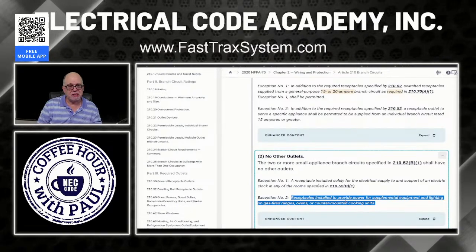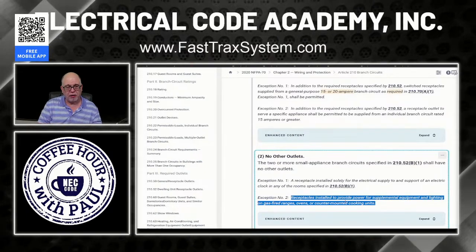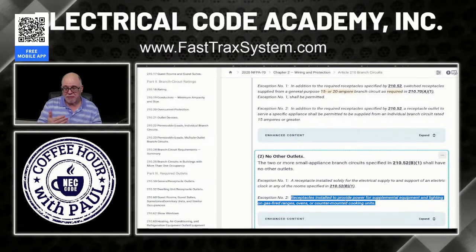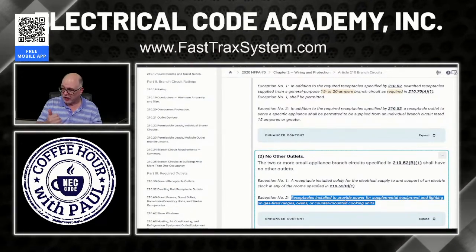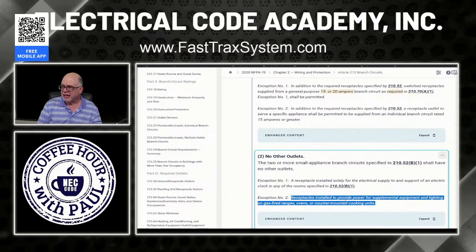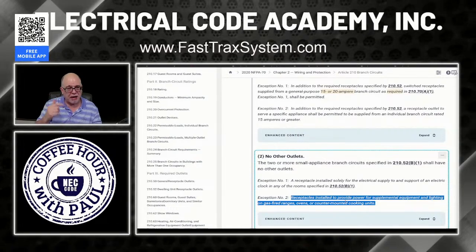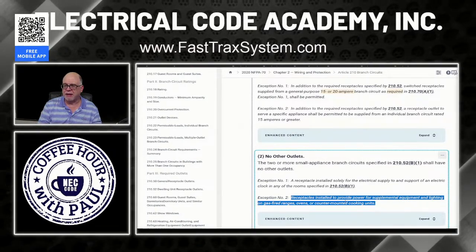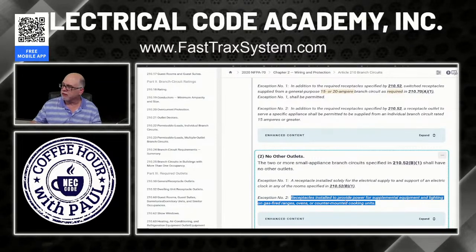Well, if that's the case, and in a lot of homes with gas cooking, you'll have a receptacle down there to plug in the electric igniter. Can that be on the small appliance branch circuit? Absolutely. Based on what? Exception number two. Those are the only two occasions where you can have other things on that small appliance branch circuit. Can't have microwaves, can't have hoods, hood fans, none of that type of thing can be on it, okay? That's very important for you to realize, all right?